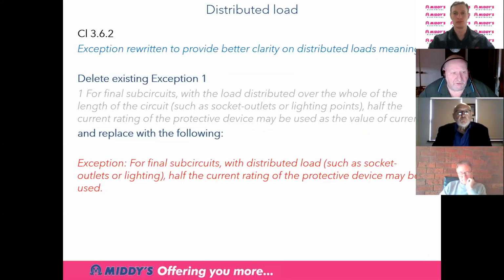Exception rewritten to provide better clarity. There's always been an exception that you can use half the circuit breaker size when calculating your voltage drop in relation to distributed loads along a circuit. Well, we discovered that people were assuming that meant they had to be evenly distributed, so every 2 metres I had a socket outlet. That was never the intent. So we've rewritten it in red to make it clearer that now, providing that they are spread along the circuit, you can actually apply half the circuit breaker rating for the voltage drop for the current rating. Next slide, thank you.